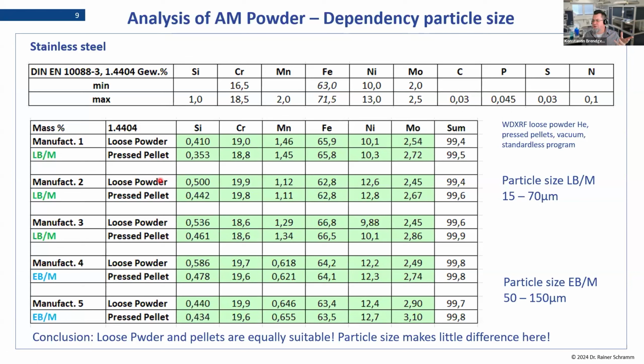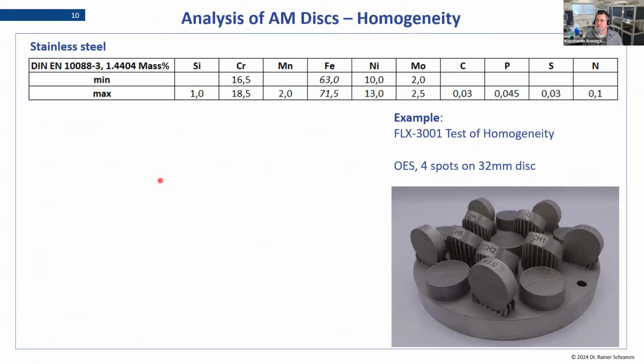By equipment, maybe just to clarify, for example, if you don't have the option to do a helium flush in your machine, then obviously loose powder is a bad idea, and you would have to do pressed pellet and vacuum. But depending on the equipment you have, if you can do both, loose powder will probably give you the same results as a pressed pellet, so you can skip that step.